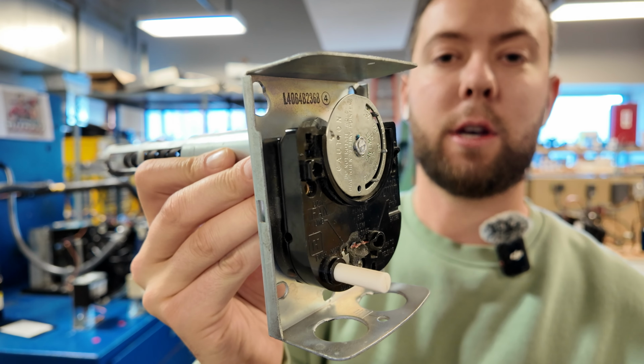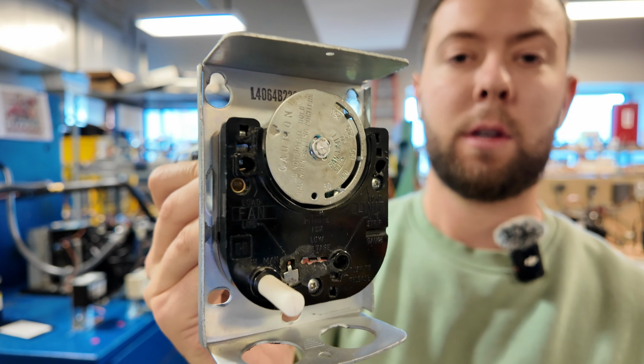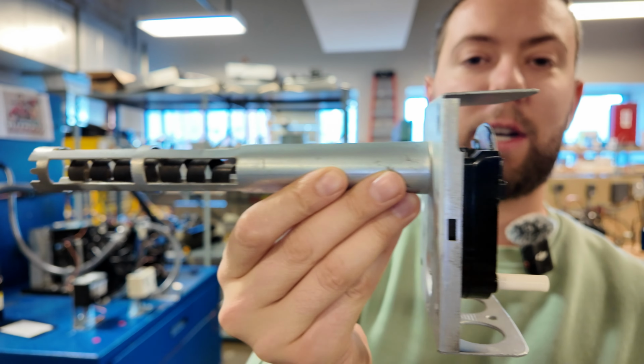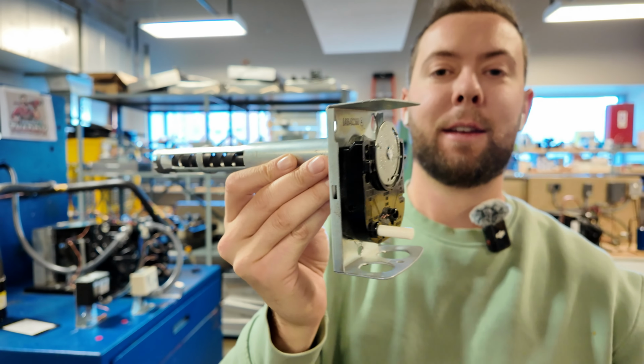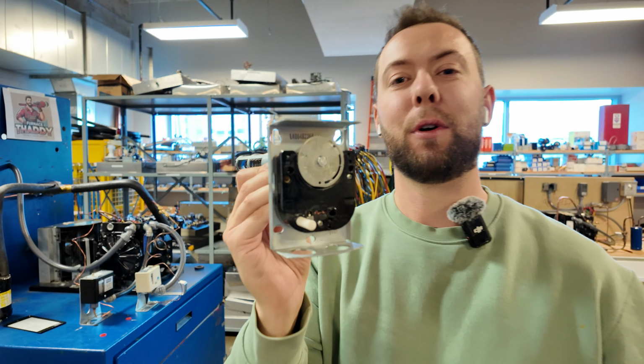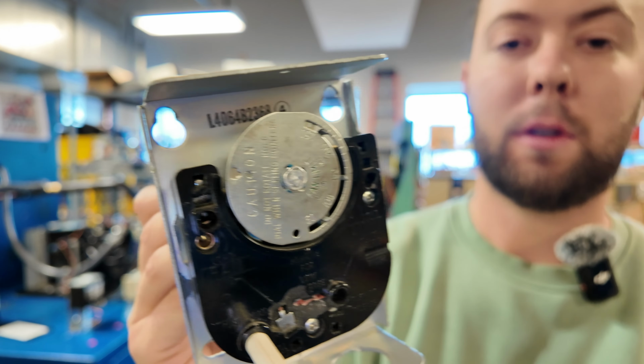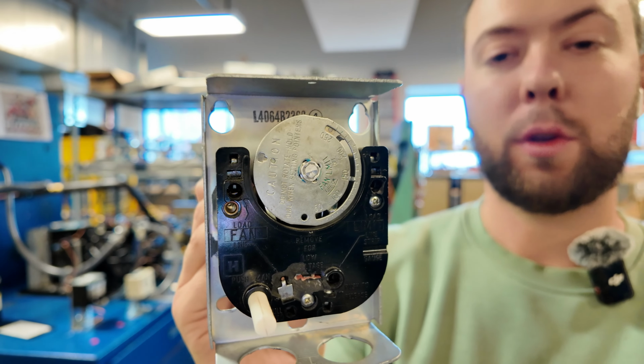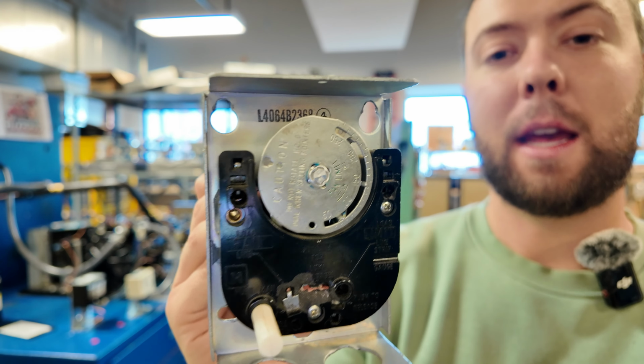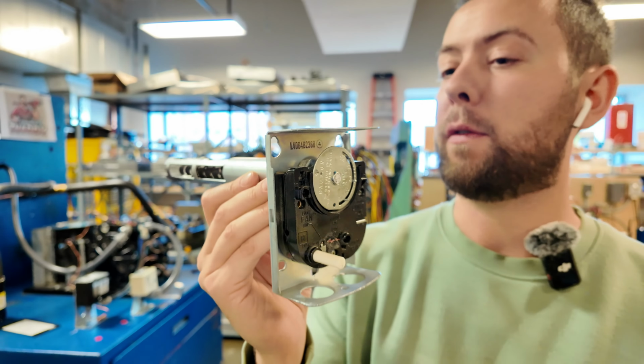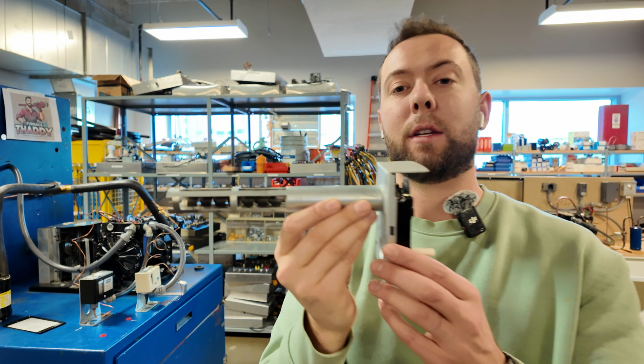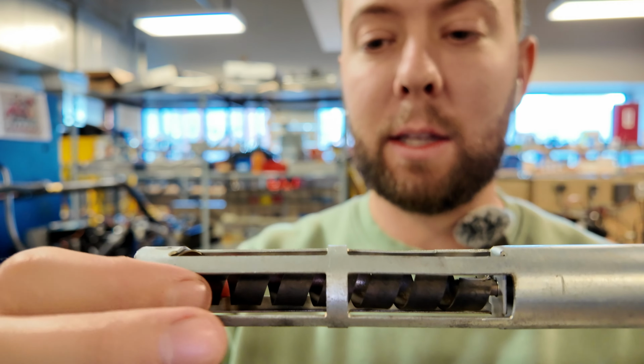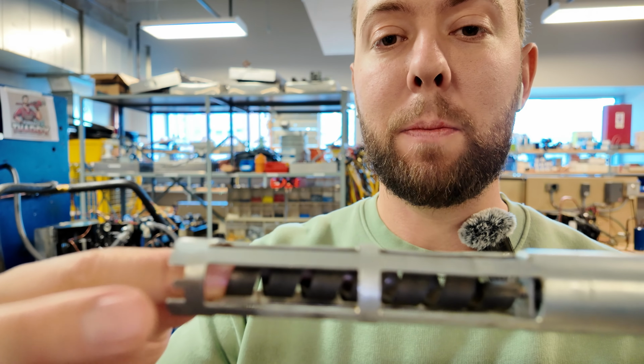So today we're going to talk about fan controls. You don't see these very often on equipment anymore, as they're old school, on old furnaces. A fan control controls cut out, cut in, and high limit for your furnace on an older furnace. So on this side, you're going to see this spiral bimetal strip here.